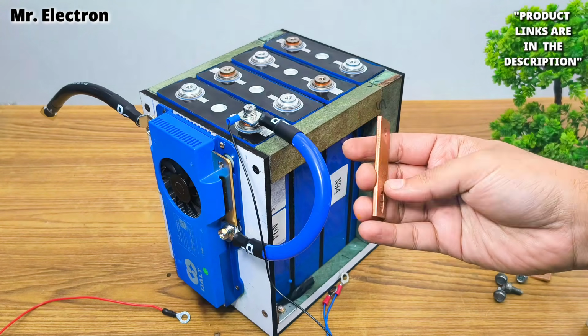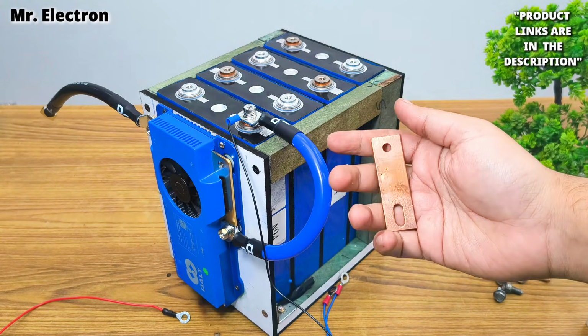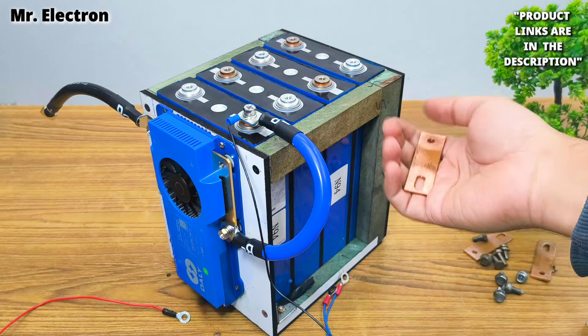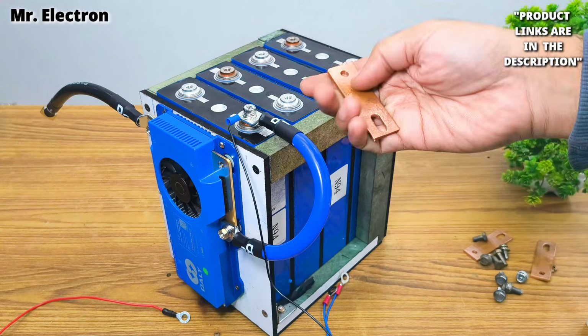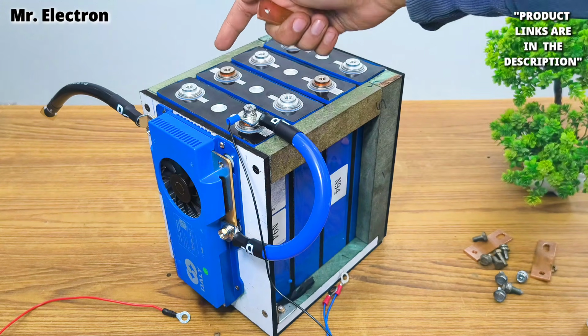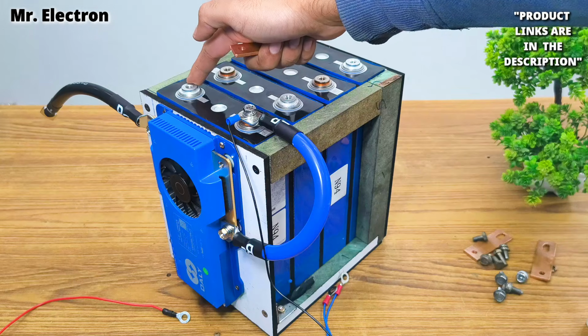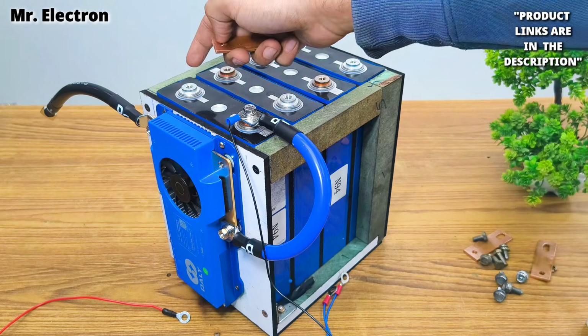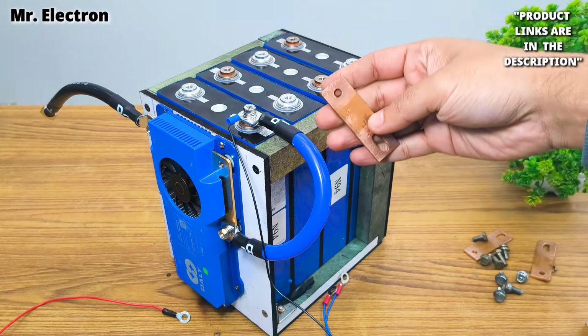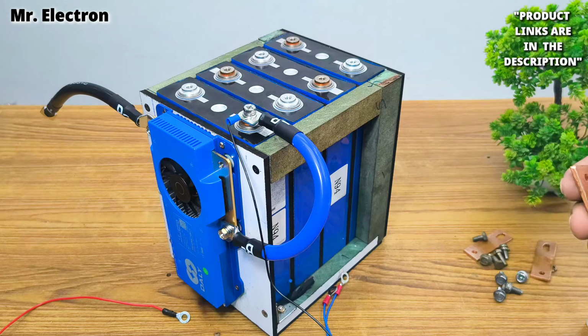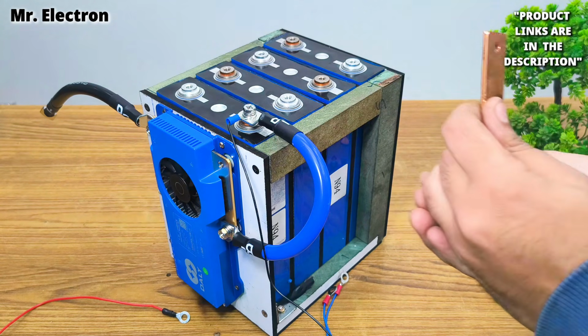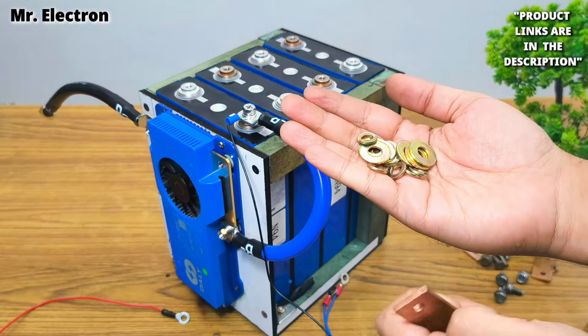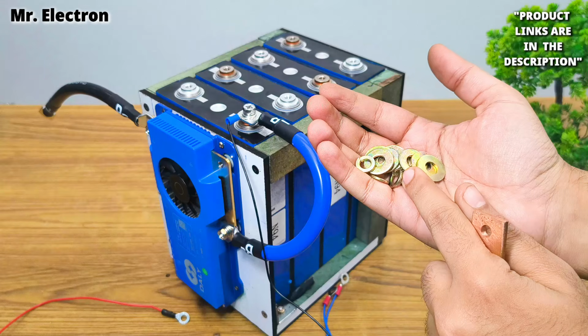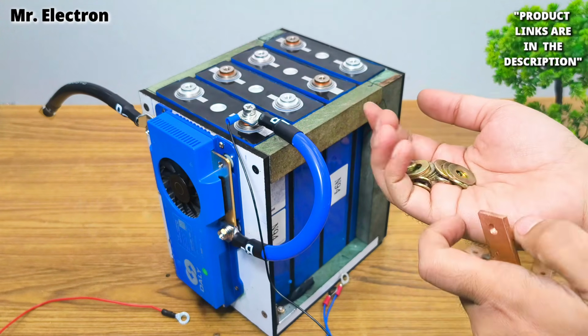These bus bars are not coated with anything, neither nickel nor tin. So we cannot connect them directly to the terminals, because one terminal is aluminum, and copper and aluminum don't go well together—there is corrosion. So what I'm going to do is use zinc-coated washers in between the bus bar and the aluminum terminal.